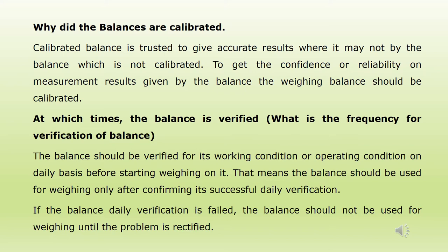The balance should be verified for its working condition on a daily basis before starting weighing. That means the balance should be used for weighing only after confirming its successful daily verification. If the daily verification fails, the balance should not be used for weighing until the problem is rectified.